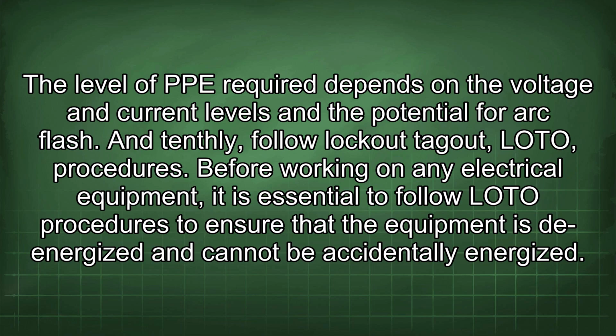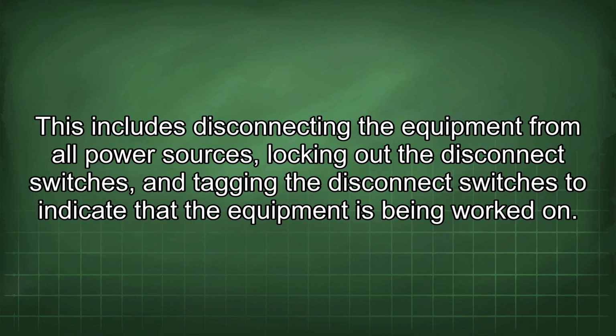And tenthly, follow lockout tagout (LOTO) procedures. Before working on any electrical equipment, it is essential to follow LOTO procedures to ensure that the equipment is de-energized and cannot be accidentally energized. This includes disconnecting the equipment from all power sources, locking out the disconnect switches, and tagging the disconnect switches to indicate that the equipment is being worked on.